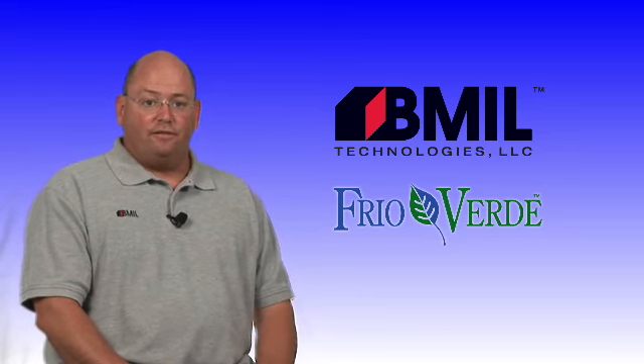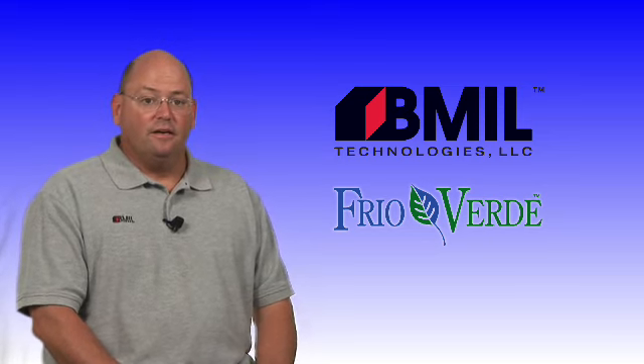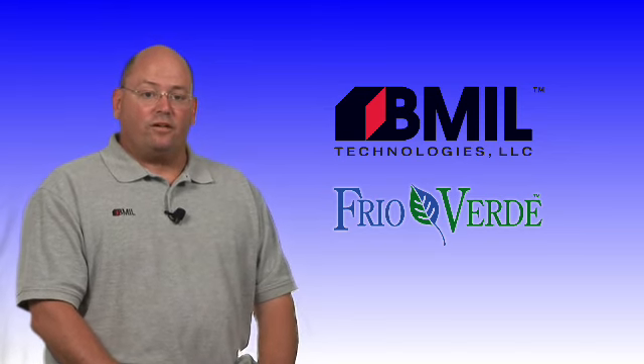EER stands for Energy Efficiency Ratio, and it's a measure of the efficiency of refrigeration systems. The higher the EER, the more efficient the system. R410A systems run at an EER of 10 to 16, while R404A refrigeration systems run at a lower EER. R404A medium temperature refrigeration systems run at an EER of 5 to 9, and low temperature refrigeration systems run at an EER of 2 to 4.